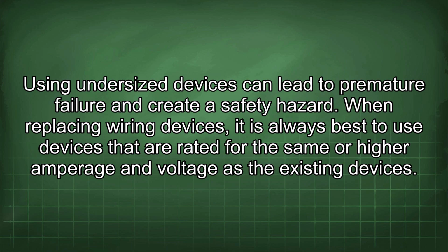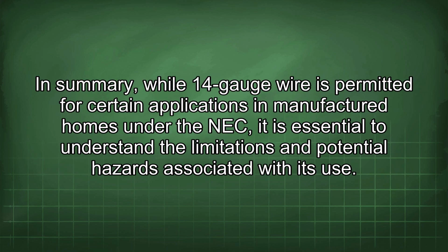Using undersized devices can lead to premature failure and create a safety hazard. When replacing wiring devices, it is always best to use devices that are rated for the same or higher amperage and voltage as the existing devices. In summary, while 14-gauge wire is permitted for certain applications in manufactured homes under the NEC, it is essential to understand the limitations and potential hazards associated with its use.